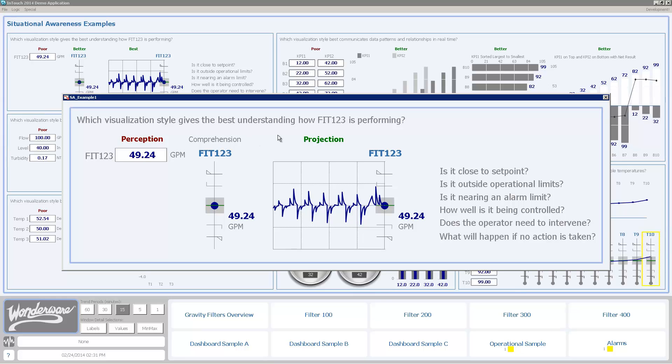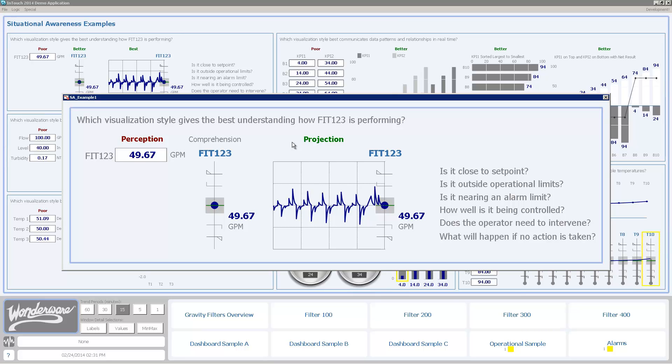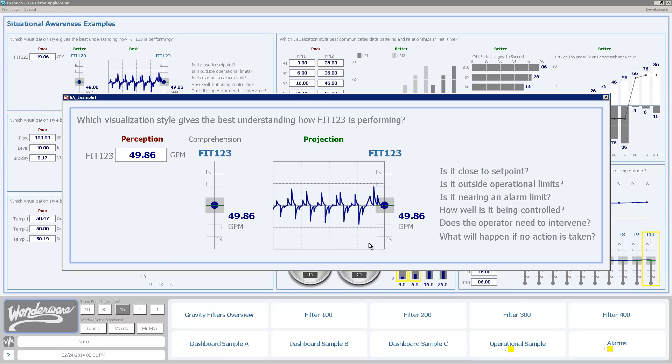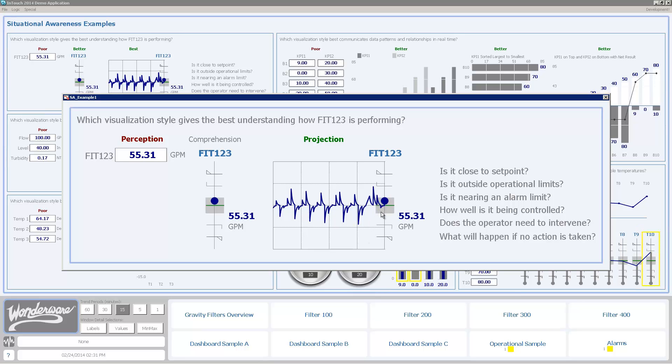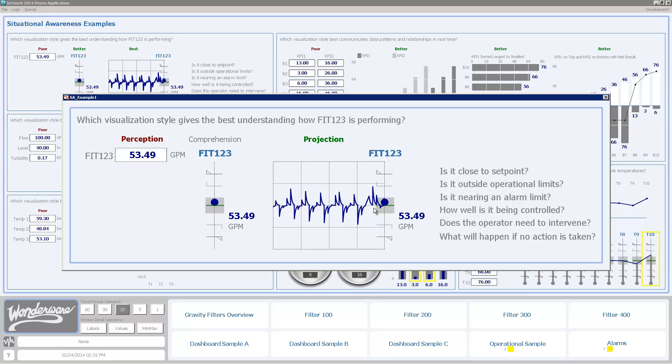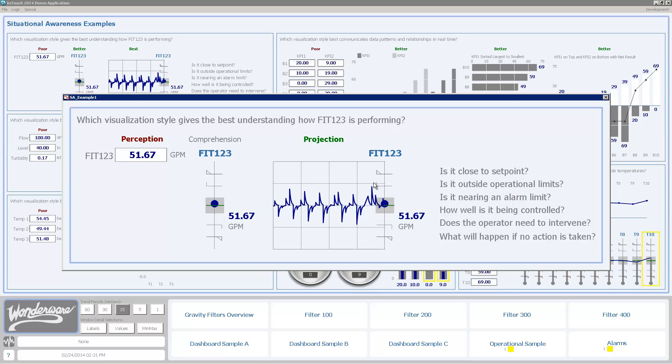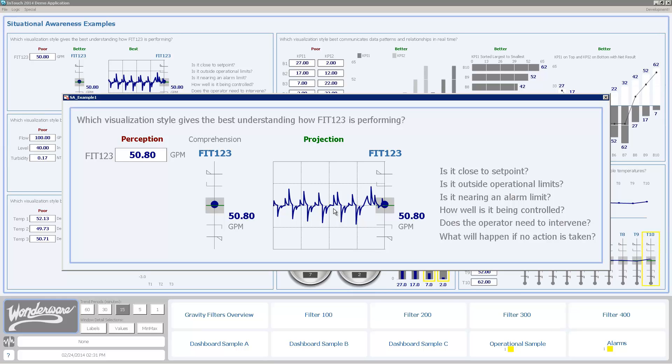Going to the third level, what we're referring to here as projection, starts to give me an understanding of how can I expect this to behave in the future. With this one specifically, we're showing a trend. This trend is showing you not just where you are in relation to that meter, which is still present, but now with projection we're able to see the rate at which I'm moving. I can look at the past and see how things are going to be acting in the future. I can see that this has been wavering pretty far outside those operational limits, not going into the alarm limits but getting pretty close, so I'm not really controlling the signal very well.